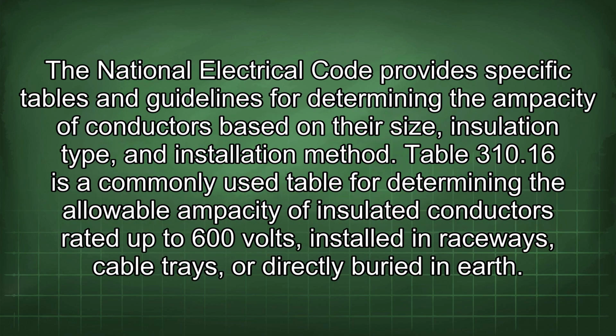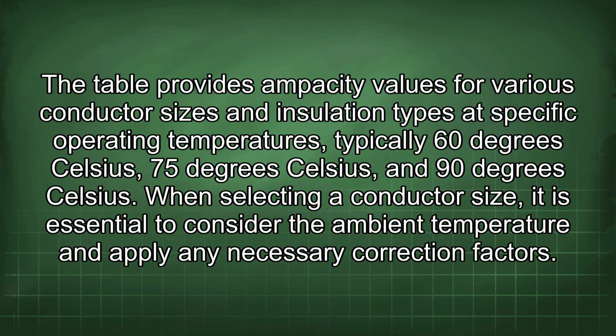The National Electrical Code provides specific tables and guidelines for determining the ampacity of conductors based on their size, insulation type, and installation method. Table 310.16 is a commonly used table for determining the allowable ampacity of insulated conductors rated up to 600 volts, installed in raceways, cable trays, or directly buried in earth. The table provides ampacity values for various conductor sizes and insulation types at specific operating temperatures, typically 60 degrees Celsius, 75 degrees Celsius, and 90 degrees Celsius.